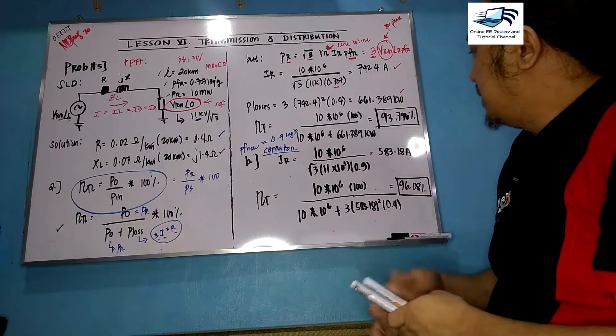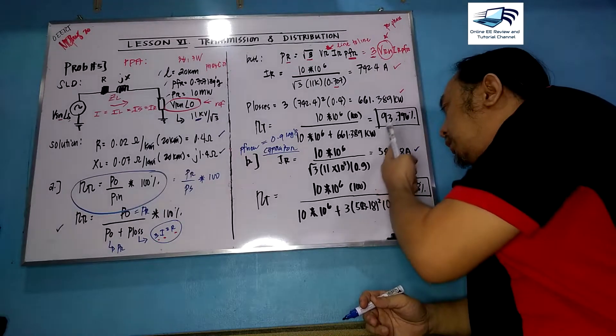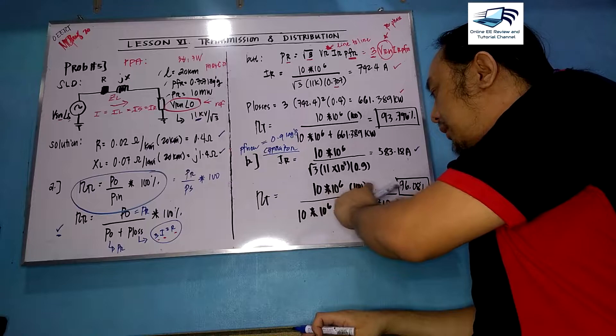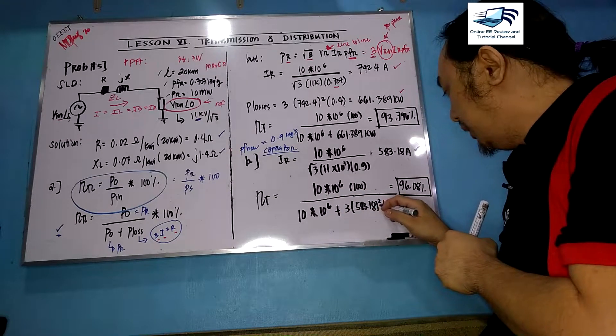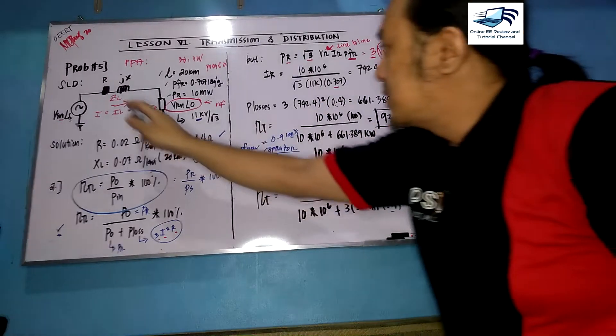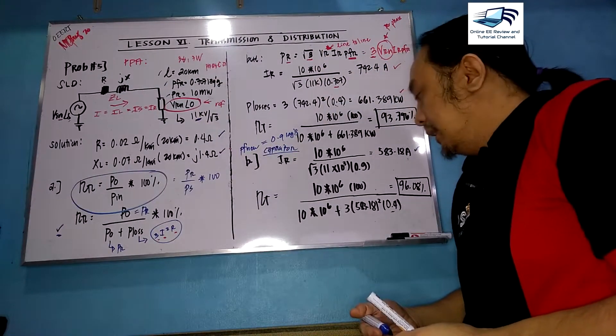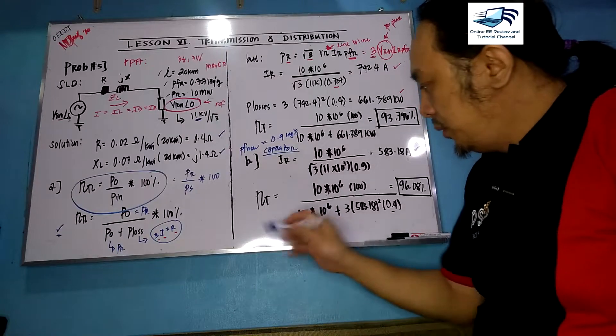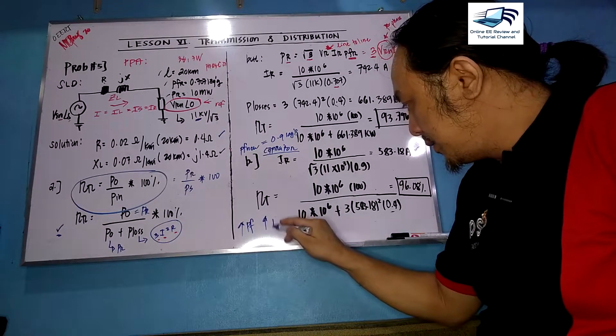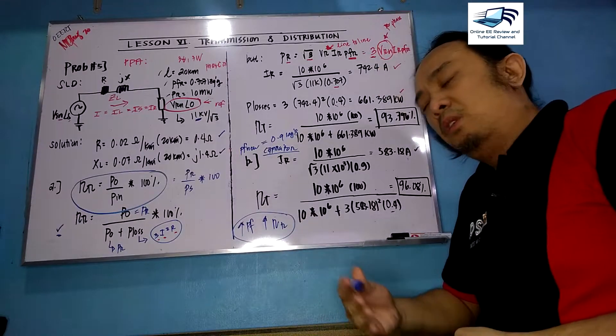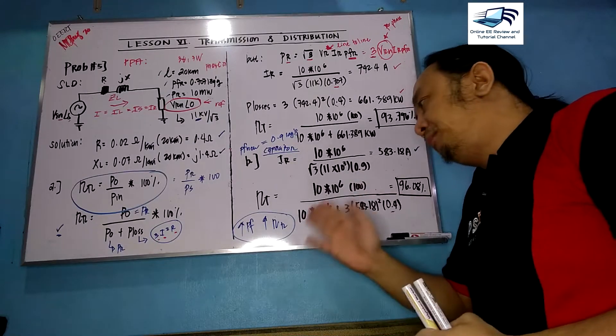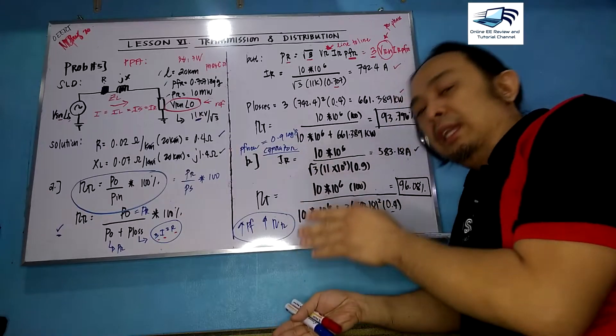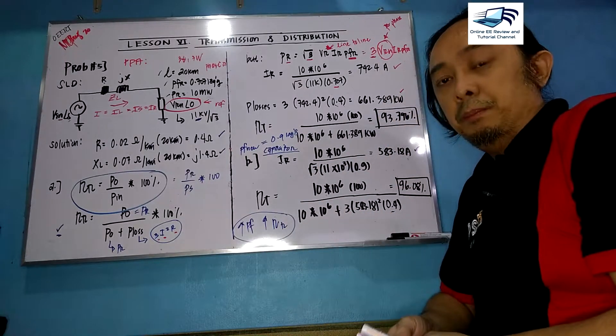With power factor 0.9, the new current is 583.18 amperes. Substituting into the efficiency formula: 10 megawatts over (10 megawatts plus 3 × (583.18)² × 0.4) times 100, the answer is 96 percent. The moral lesson: if you increase the power factor — the cosine of the angle between voltage and current — you increase the efficiency of the transmission line system.